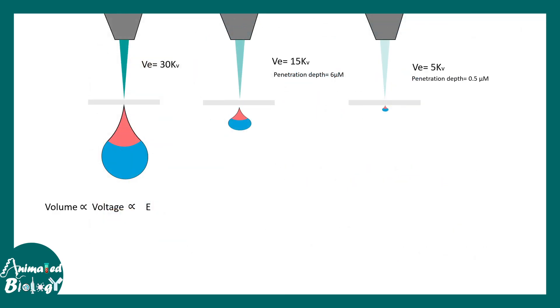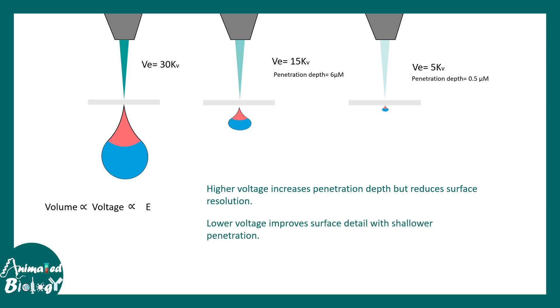Depending on the acceleration voltage of the electrons, the volume of imaging and the penetration depth vary. At 15 kV the penetration depth is about 6 microns, whereas at 5 kV it becomes about 0.5 microns. So: higher voltage increases penetration depth but reduces surface resolution, while lower voltage improves surface detail and gives shallower penetration. What we choose really depends on what we are trying to image.